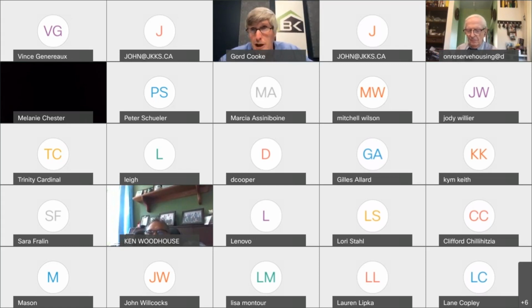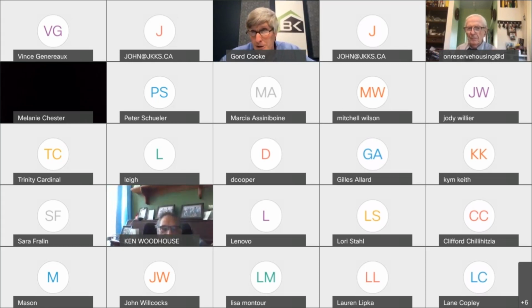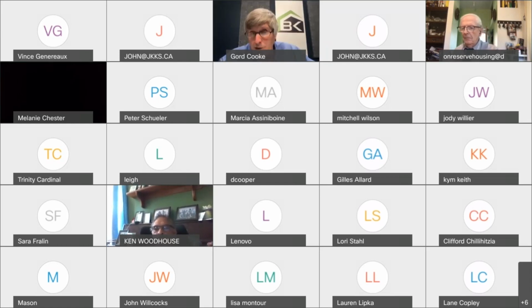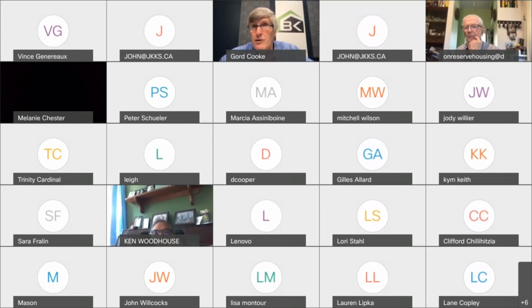With an HRV I'm going to recover 70% of that. In southern climates, like Florida, they worry not so much about the temperature difference but the moisture difference - the humidity. So they look for a device with a latent component, able to recover moisture from an airstream - that's called an ERV. An ERV recovers heat in both sensible and latent form. You would want an ERV in a climate with high humidity in the summer and air conditioning. If you're not air conditioning, there's limited value to an ERV. In community centers, office buildings and so on, if you're air conditioning and looking to ventilate, ERV makes sense. For most community housing, we don't typically put in air conditioning - we're in a northern climate without many air conditioning days, so we probably can stay with HRV.